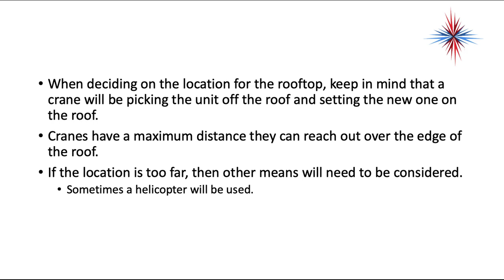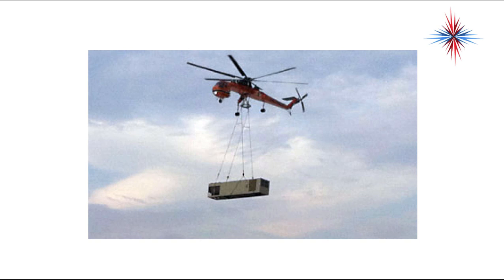When deciding on the location on the rooftop, keep in mind that a crane will be picking up the old unit off the roof and setting a new one on the roof. Cranes have a maximum distance they can reach out over the edge of the roof. If the location is too far away, then other means will need to be considered. Sometimes a helicopter will be used. Very expensive.